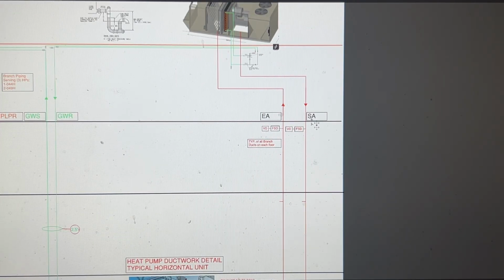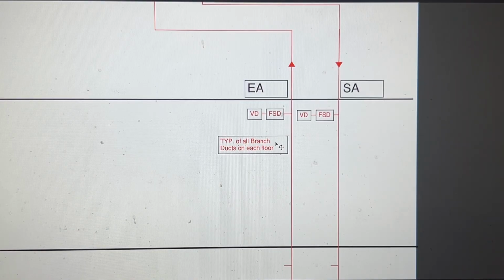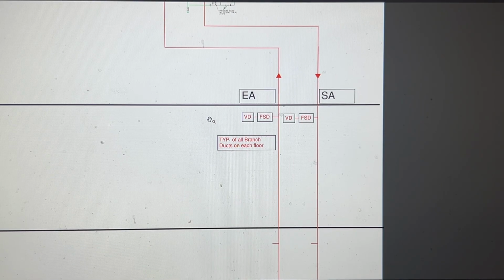So they built shafts for this ductwork on each side of the building. So we had a shaft that would have the supply air and exhaust air ductwork. What we had to do is install fire smoke dampers on all these branch lines at each floor. Those were hooked up to the fire alarm with 120 volt actuators so that those things close in the event of a fire. After that fire smoke damper, though, we had to put in volume dampers. This project was based on phases on the remodel. So every single floor that we remodeled, we had to adjust those volume dampers accordingly.